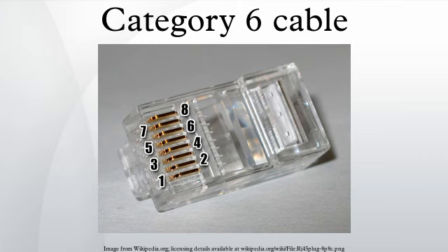Installation caveats: Category 6 and 6A cable must be properly installed and terminated to meet specifications. The cable must not be kinked or bent too tightly. The wire pairs must not be untwisted and the outer jacket must not be stripped back more than 0.5 in.